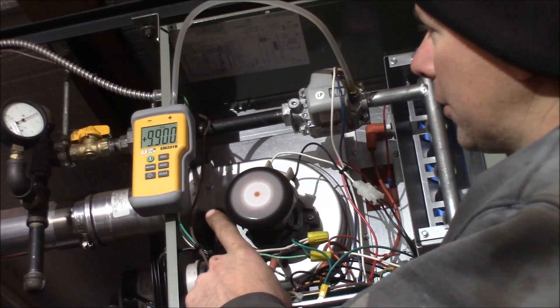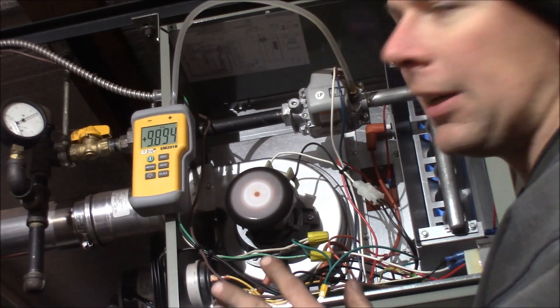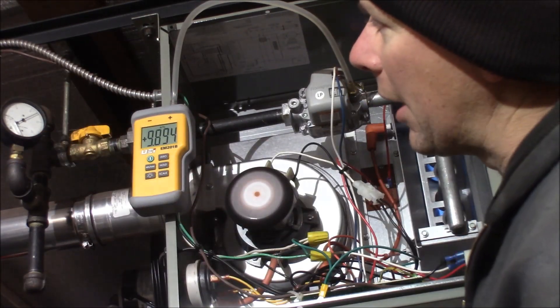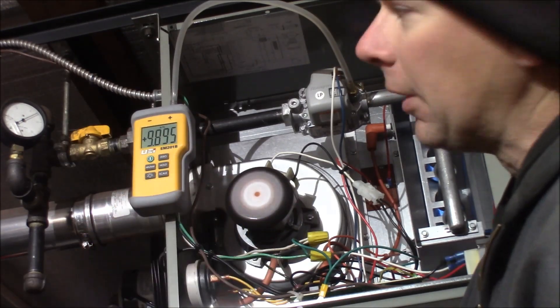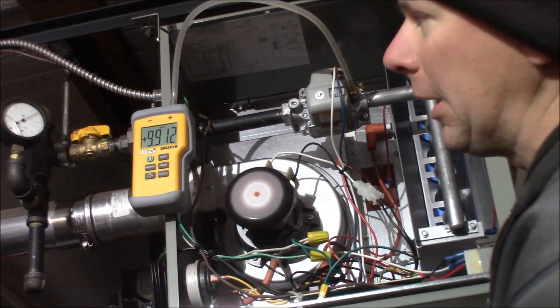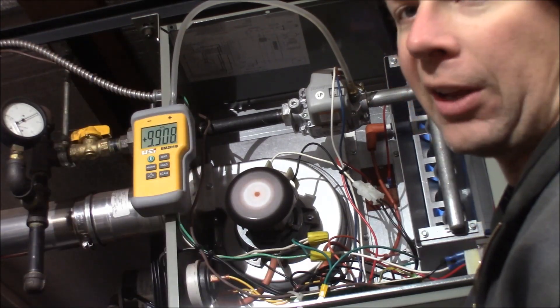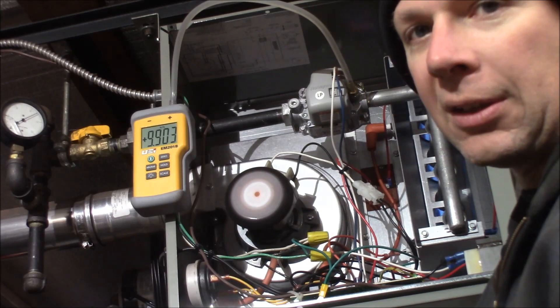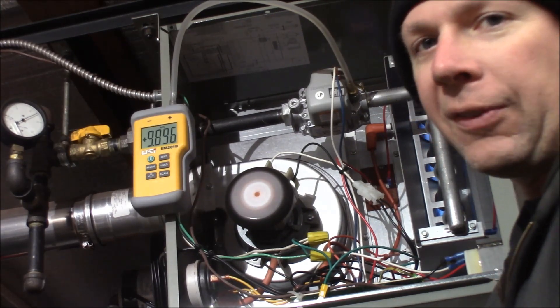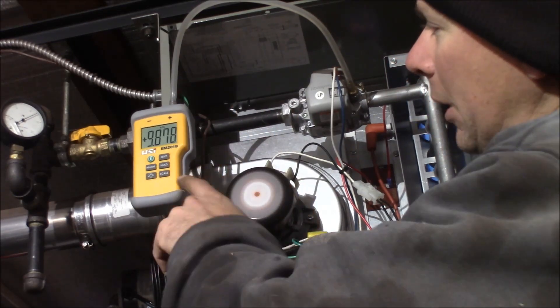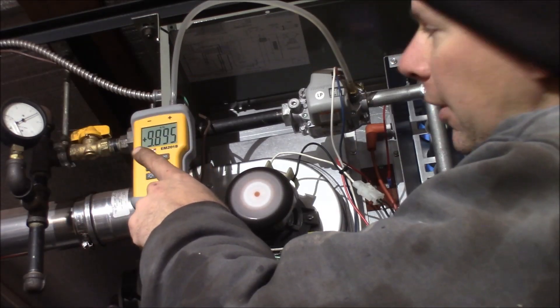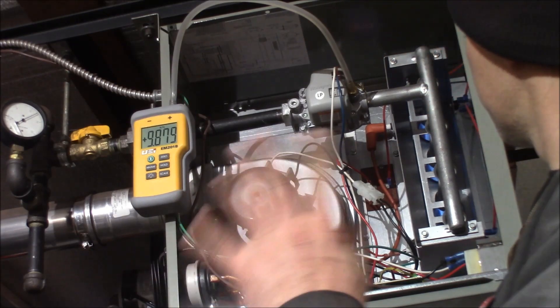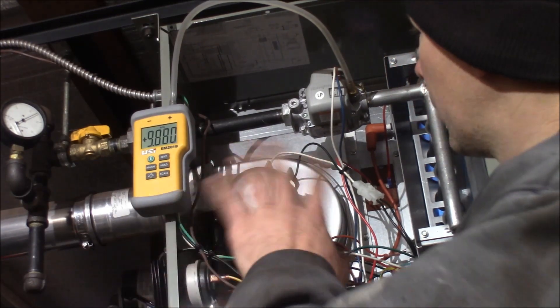My friend at work let me use this. He's an HVAC guy. He said running lean is not really going to hurt it too much. A tenth lean is fine here. So I think I'm going to leave it set now. And I can compare my gauge. As long as it's hanging around about 10 on the gauge, it's 9.89. I mean, it's close. So as long as I'm not running down at 8.5 or something like that, or it's way too lean on the analog gauge here. As long as I'm not running really lean, this will help me out. So I can watch it. And just the shade over 10 on that gauge is 9.9 here. So it's got a nice blue flame, it's making nice heat. I think we're going to be good. So that's just a quick shot. If you can get your hands on a manometer, you can set up your furnace.